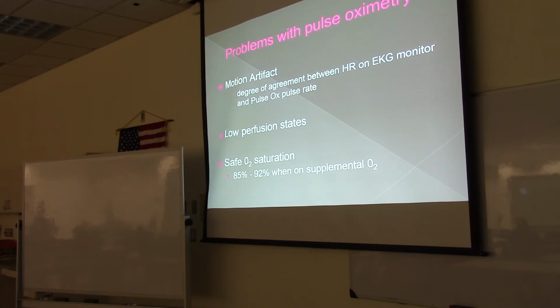With pulse oximetry, you want to make sure that your reading is accurate, because sometimes you'll get a low saturation reading, and the reason for the low reading is not because the baby is desaturating or even the adult is desaturating. It's just because your sensor isn't picking up properly. It could be cold extremities, so you don't have good perfusion going to the fingers or the hand. So one thing you can do is make sure that your waveform that displays heart rate agrees with the cardiac monitor. So that's one way to ensure that the values that you're getting are believable.